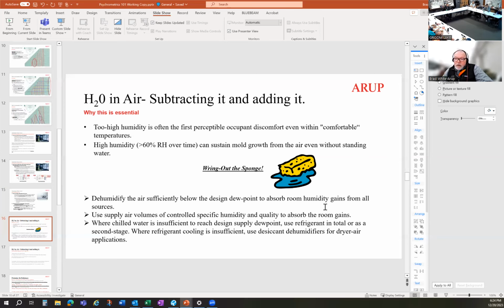they actually run two-stage. Sometimes they use two-stage cooling coils. They do a first stage and a second stage, often on completely separate circuits, and they'll trim it with the second one. They'll get that air down to 39 degrees sometimes, and they really dry it out. This is for DOAS units and so forth, because they're trying to protect the building and manage their outside air through a DOAS unit. That's where you really take a hard look at how much energy you're spending to condition your outside air.